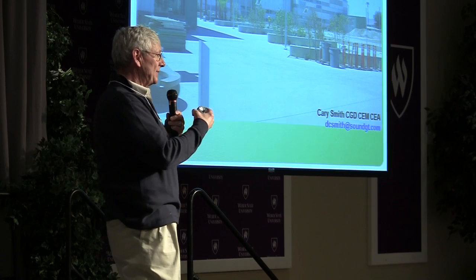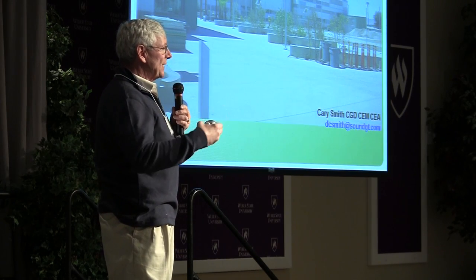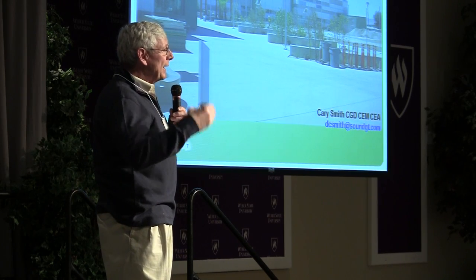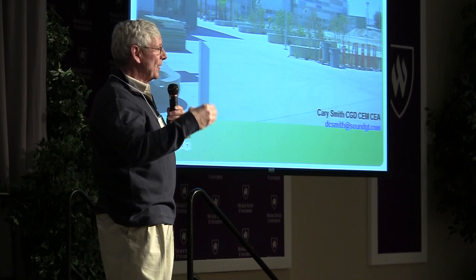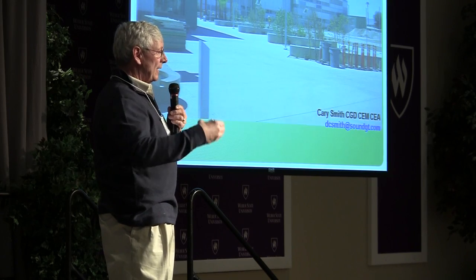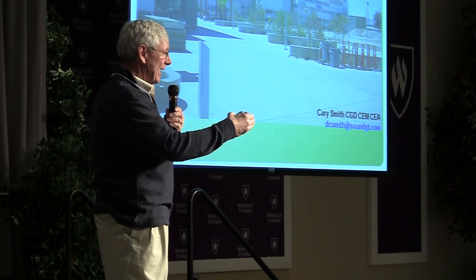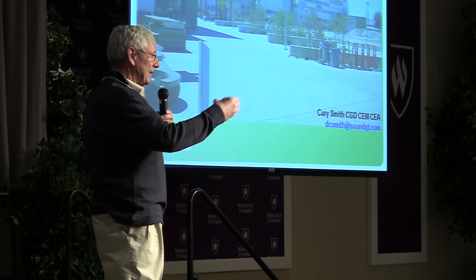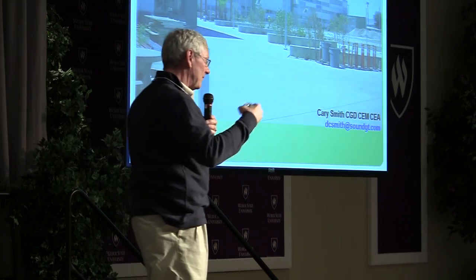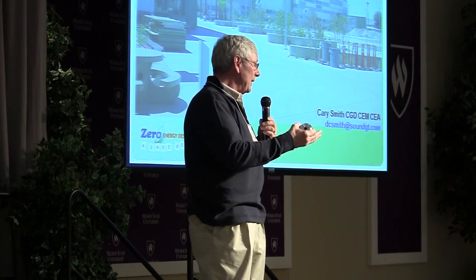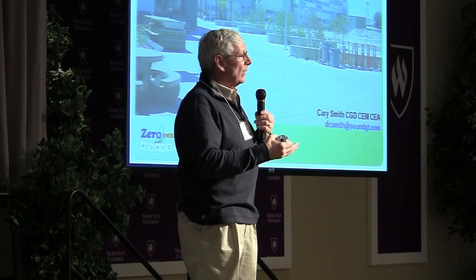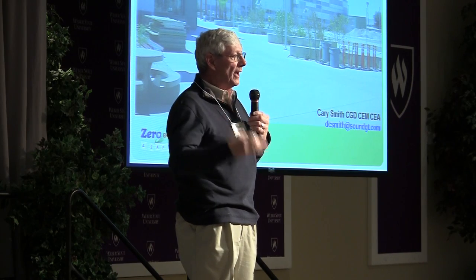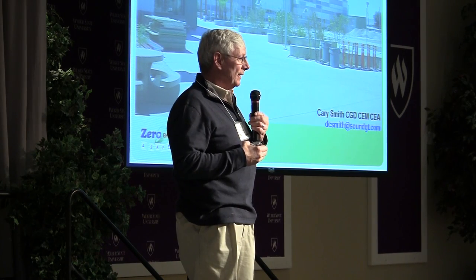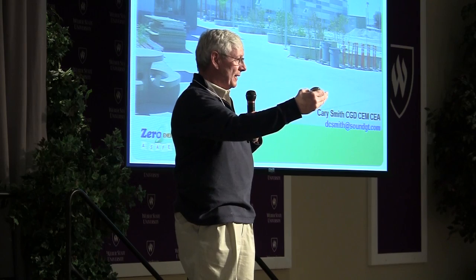Back to 'it depends.' If I get a central plant, it may be economical for me to change or take over the boiler rooms there, because that's really my limiting temperature. The fan coils might have been designed for 160 degrees for heating. Well, that fan coil still works at 125 degrees, it just doesn't put out as much energy.